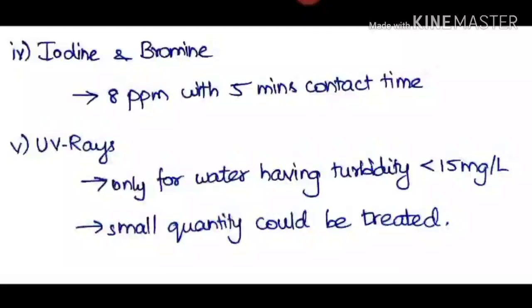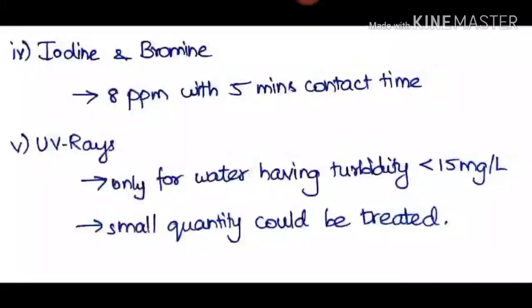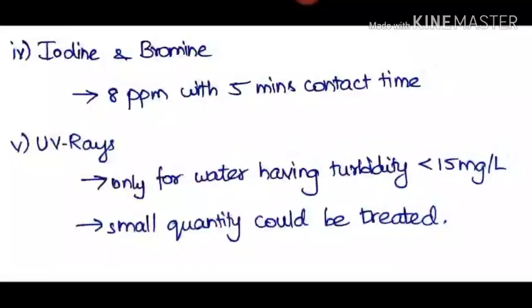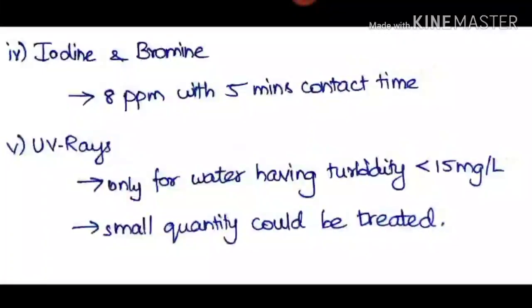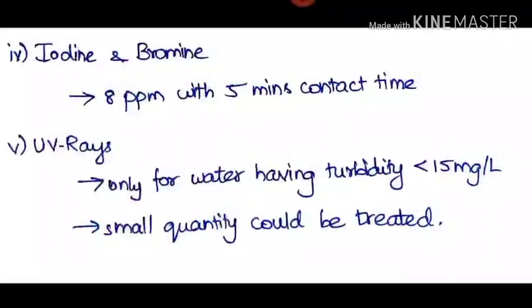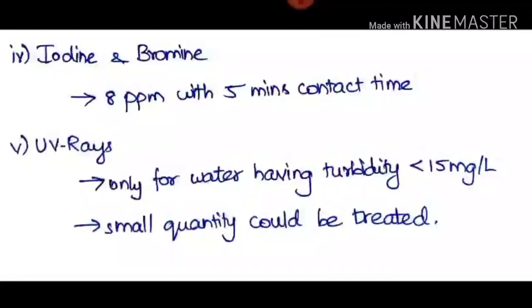The next method is UV rays. It is only used for water having turbidity less than 15 milligrams per liter, so it cannot be used for high-turbidity waters. Only small quantities can be treated because electric support is needed and the water has to be passed through the UV rays. The depth of water that can be treated is limited to nearly 10 centimeters, so this method is used for surgical purposes in hospitals.